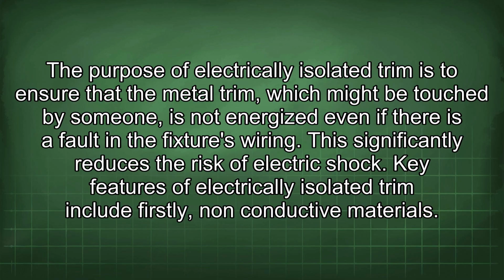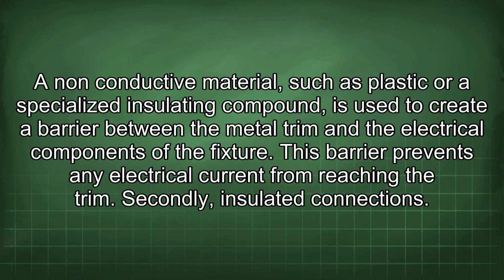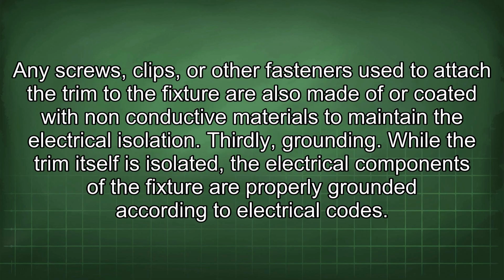Key features of electrically isolated trim include, firstly, non-conductive materials. A non-conductive material, such as plastic or a specialized insulating compound, is used to create a barrier between the metal trim and the electrical components of the fixture. This barrier prevents any electrical current from reaching the trim. Secondly, insulated connections. Any screws, clips, or other fasteners used to attach the trim to the fixture are also made of or coated with non-conductive materials to maintain the electrical isolation. Thirdly, grounding. While the trim itself is isolated, the electrical components of the fixture are properly grounded according to electrical codes.